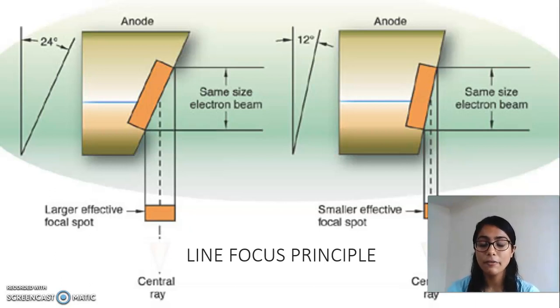The anode, the surface of the anode is inclined so that it lies perpendicular to the x-ray beam. It is called anode angle. Anode angle is crucial and its significance is smaller the anode angle, more effective the focal spot is and the radiographic quality improves.